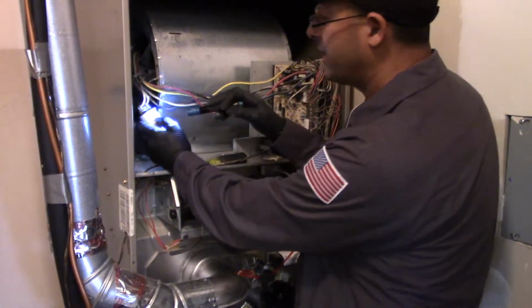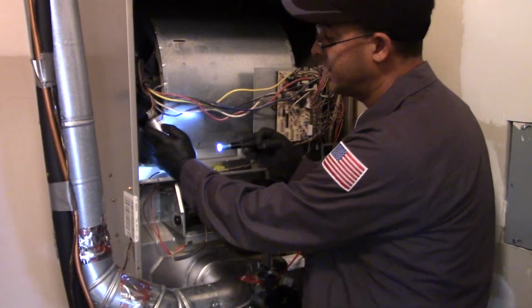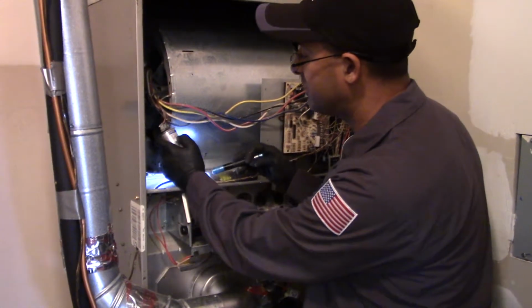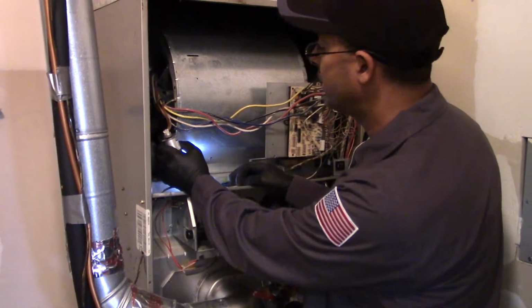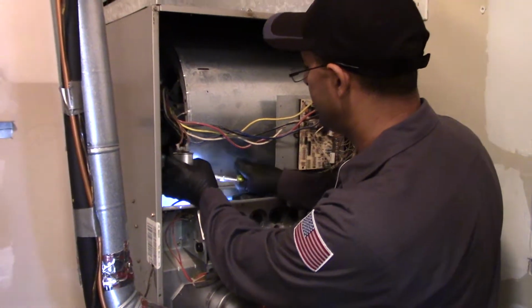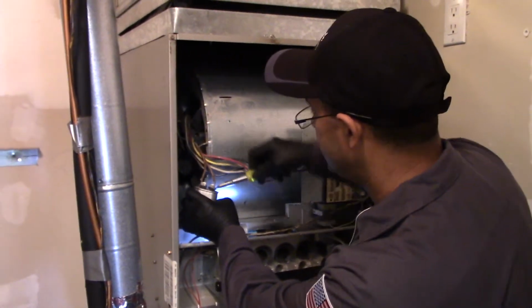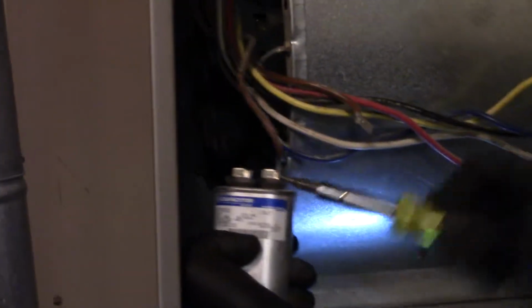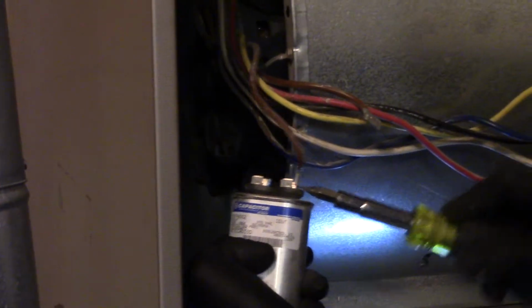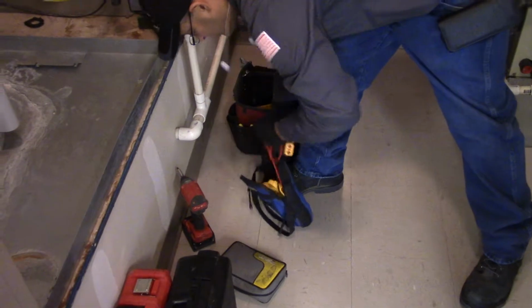So now that we know the UFs, which is 10 UF, and the voltage, plus or minus 6%, what I'm going to do now is go ahead and remove this capacitor by taking off the leads. I still just use my screwdriver for safety. I'm going to take off these leads, so I've got my capacitor there. I'm going to grab my meter and connect my meter leads and get it ready.